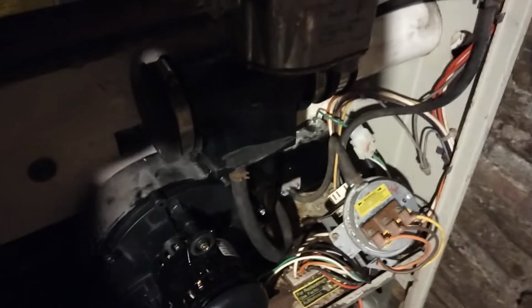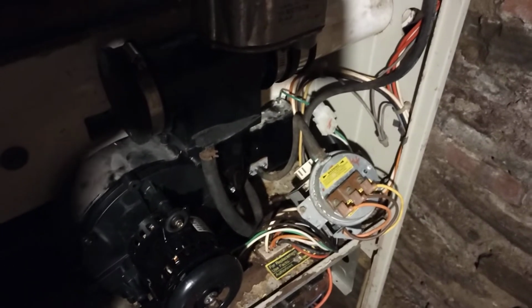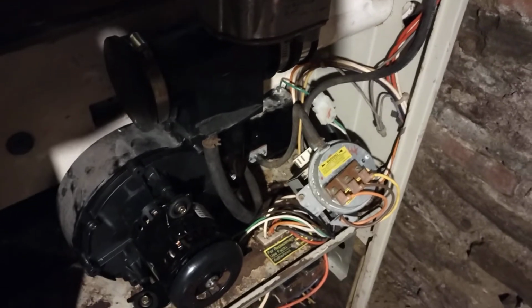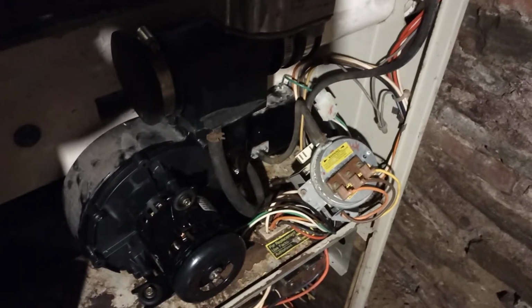Now we did a little more testing. The furnace wouldn't start, so we replaced this thing here, and tested this thing here. That was no good, it had a hole in it. We had that spare one over on the other furnace, which we took over and put over here. Still wouldn't start. Now the very next thing we did was we took the top off here.